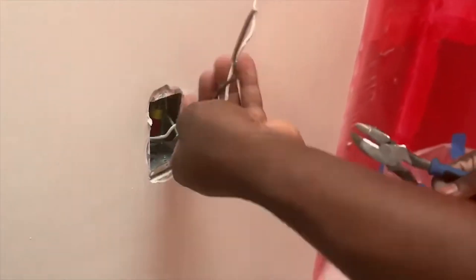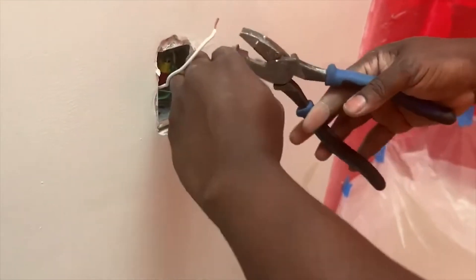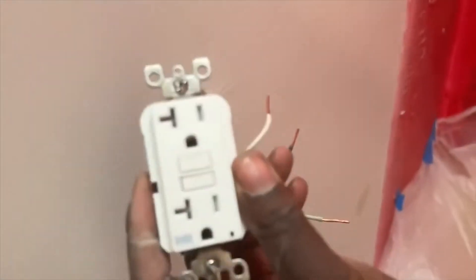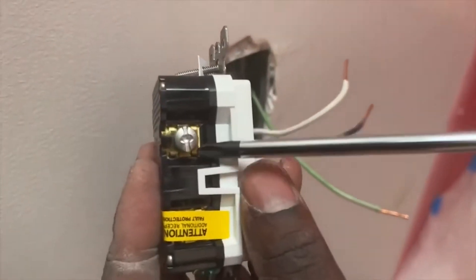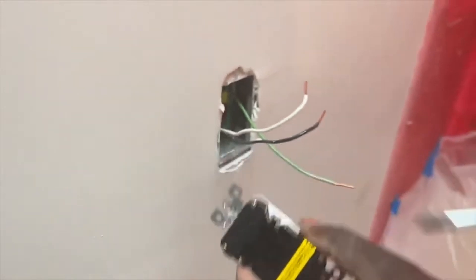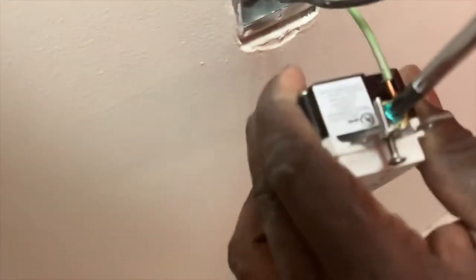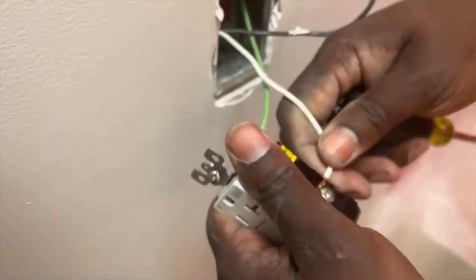Some GFCIs you don't have to create a hook — you just strip the wire and push it under the screw terminal. I'm using a 20-amp GFCI, outdoor WR which stands for weather resistant. I typically love using those in my bathroom even though it's not required — you could use a regular standard GFCI — but I prefer a weather resistant type in the bathroom.